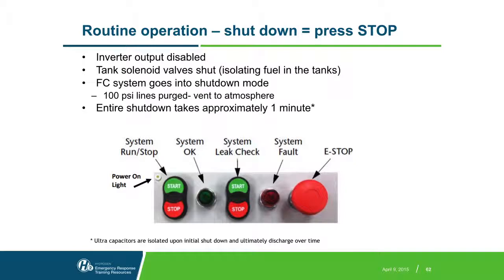On shutdown, the power from the inverter, the output power, is interrupted. The fuel is isolated in the tanks because those valves, activated by the 24-volt system and normally closed, are shut, so it isolates the fuel. The fuel cell system goes into shutdown, and the residual fuel in that low pressure line that's delivering the hydrogen to the fuel cell stack is purged. So there's no residual fuel in the lines. This whole thing takes about a minute to shut down.